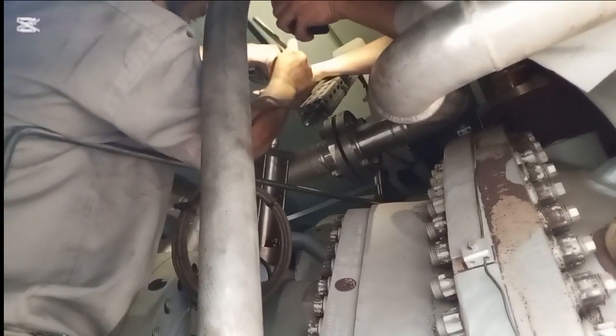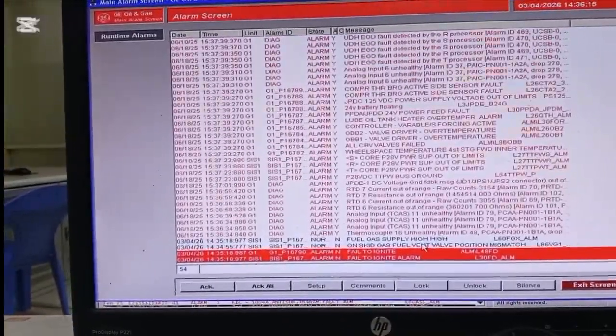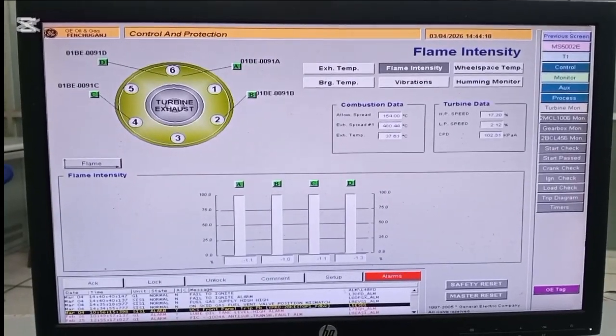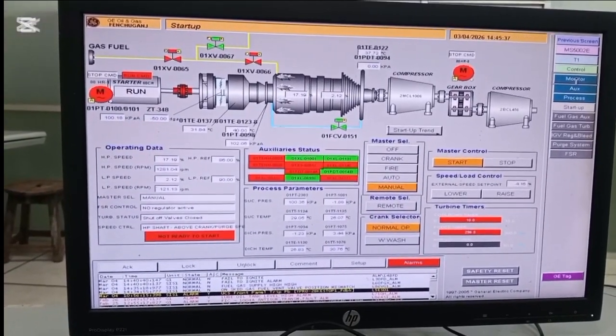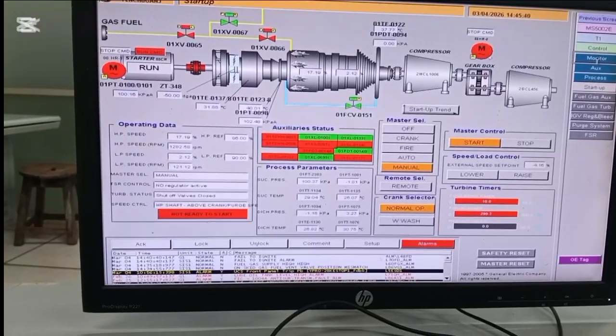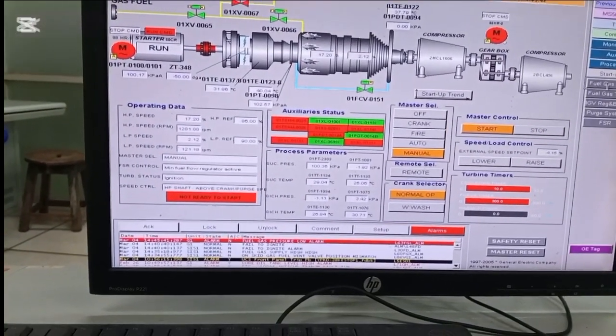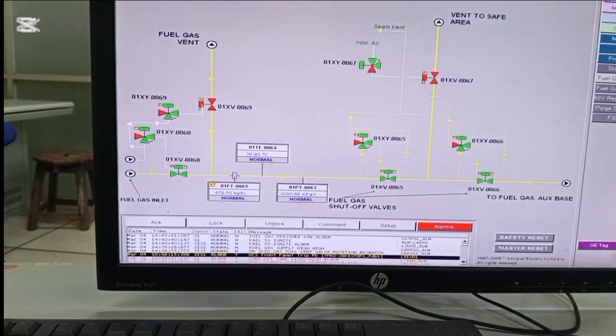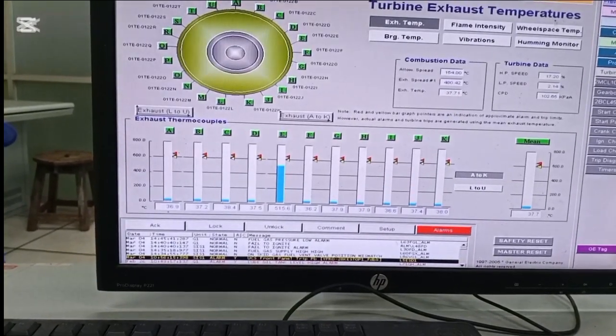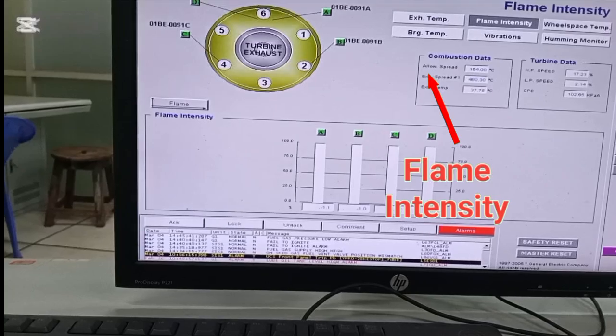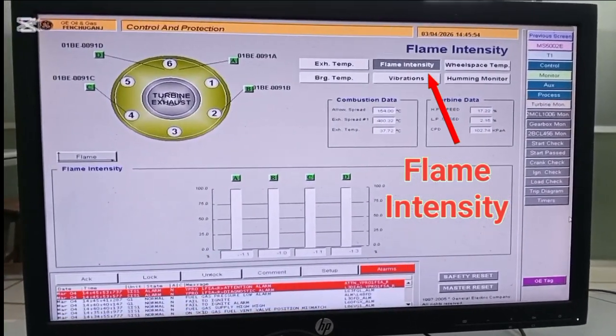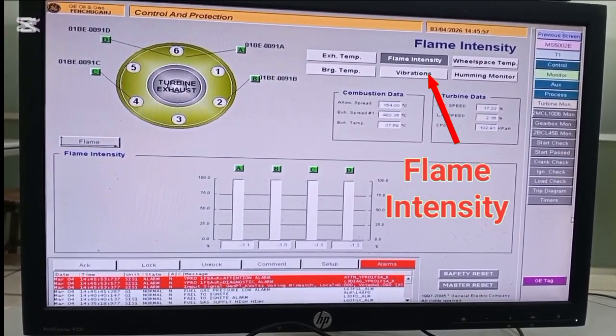This is fitted to the gas turbine, and this is the connection junction box. There are 2 spark plugs, one connected on the upper side and another on the lower side. After cleaning, we started the gas turbine again, and we saw that everything is okay. Block valve and vent valve are okay, but flame intensity is not present here. So you see there is no flame intensity, so the boiler is not fired.